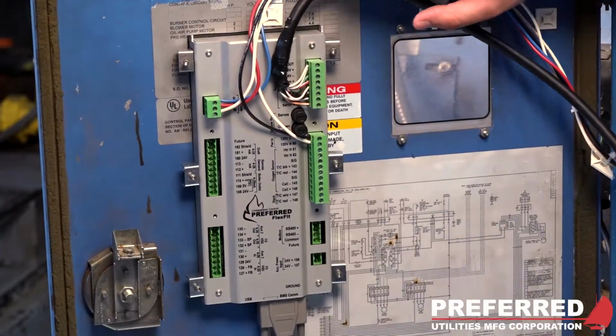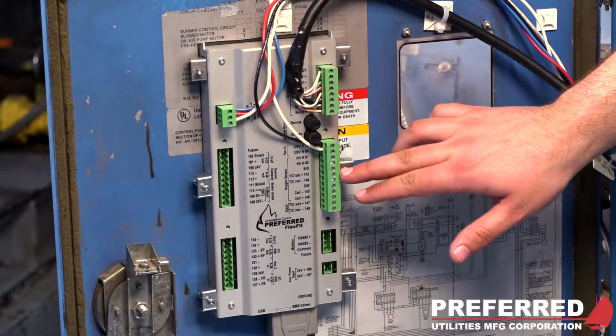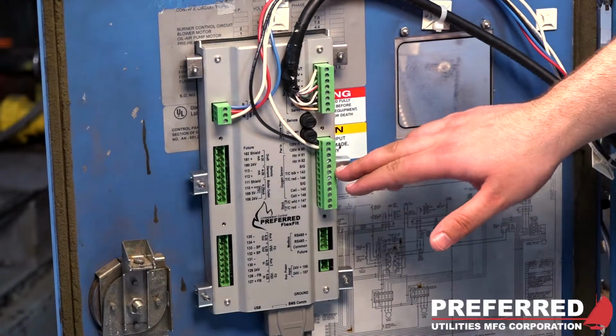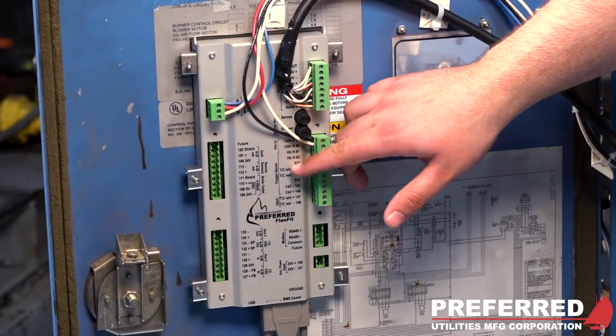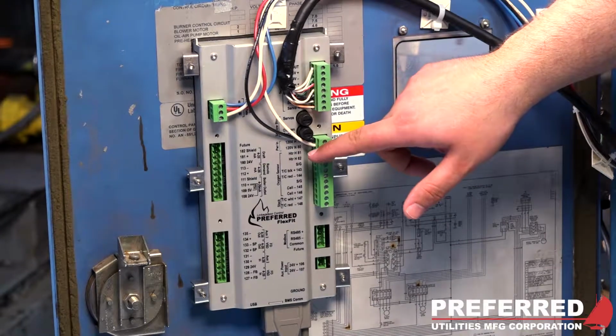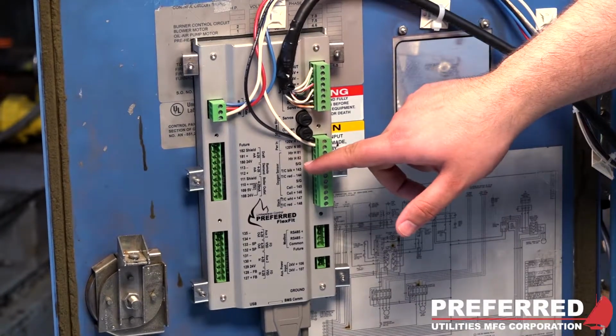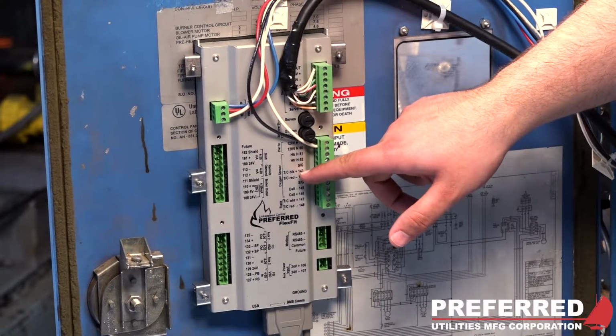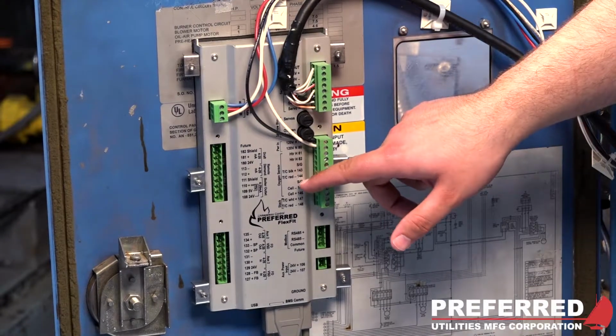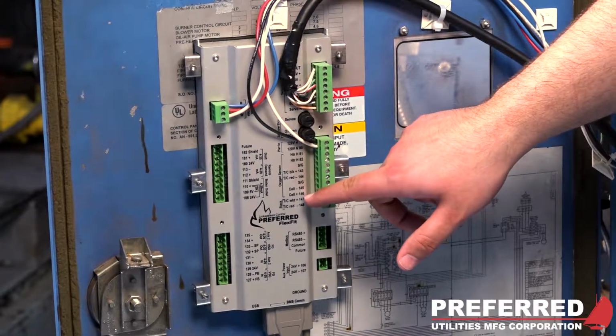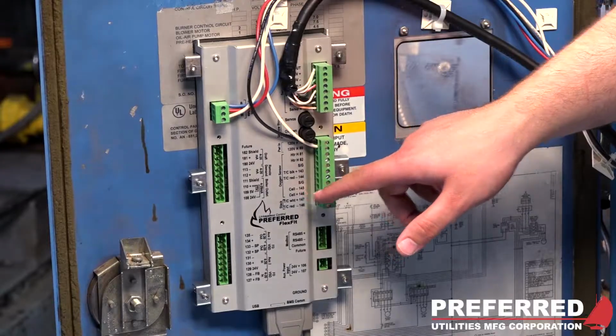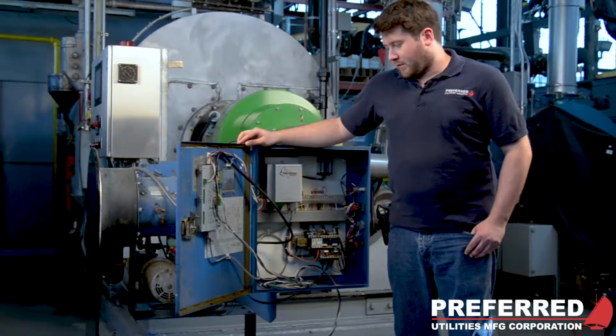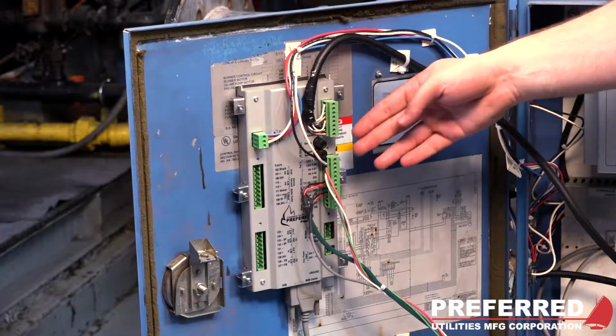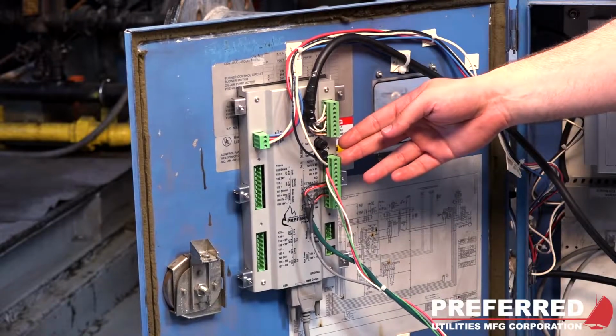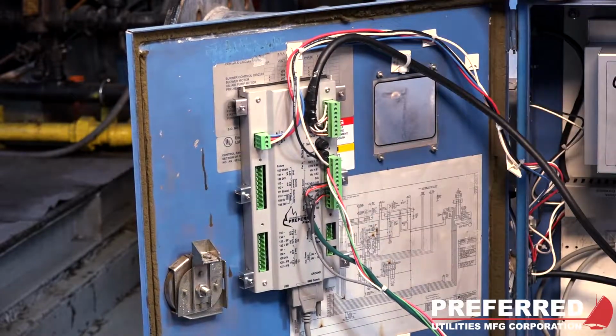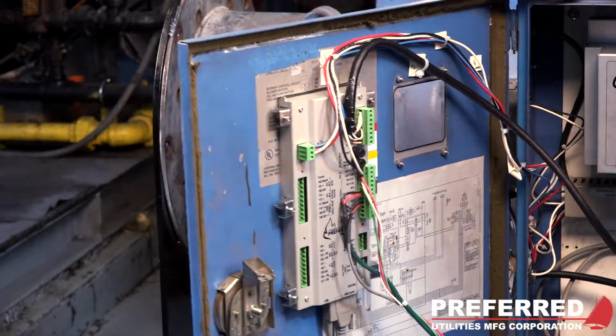The wiring will be placed into this terminal strip here on the right hand side, and it's clearly labeled oxygen sensor. You've got two terminals for your heater, one for your shield, two terminals positive and negative for your thermocouple, another shield, and then a positive and negative for the O2 cell. You can consult your manual for your complete wiring directions. The completed wiring should look like this. And now we can move on to setting up the controller.